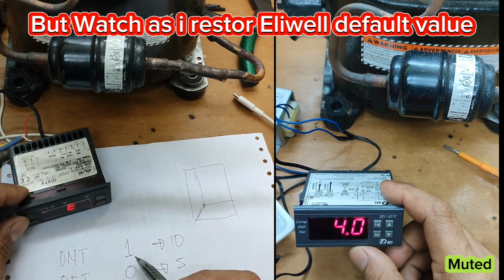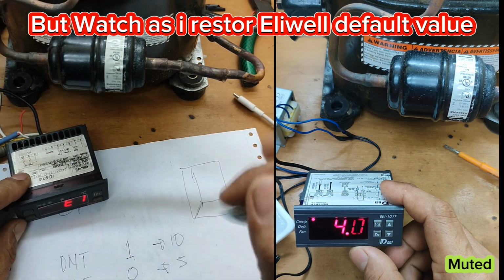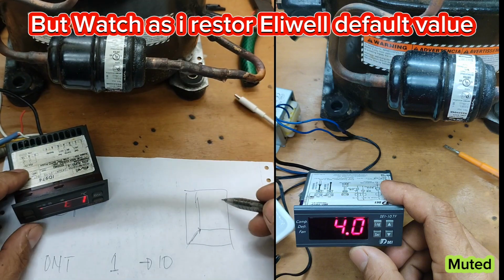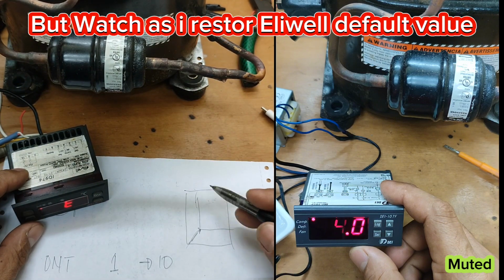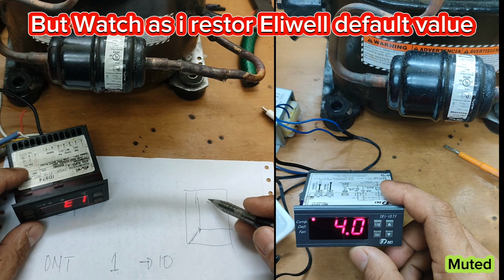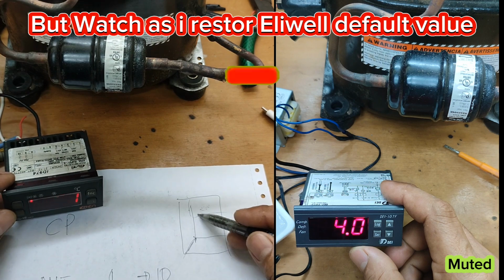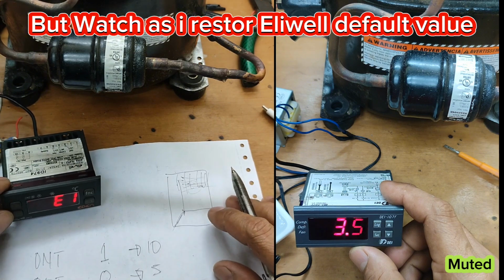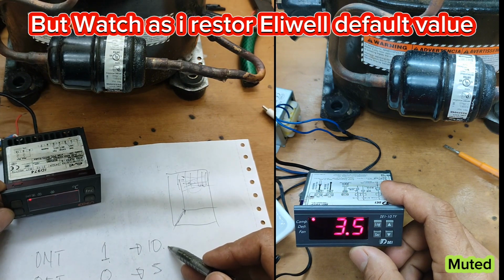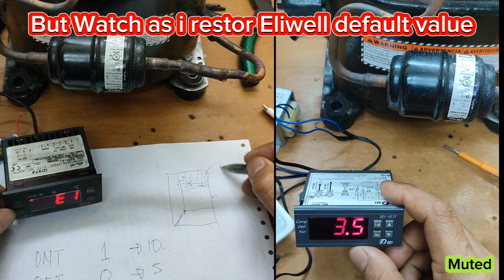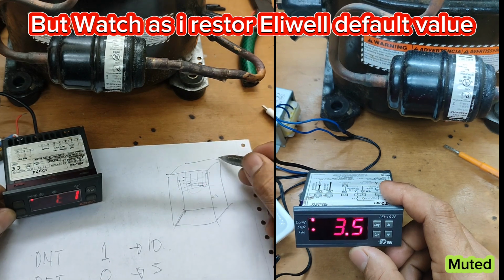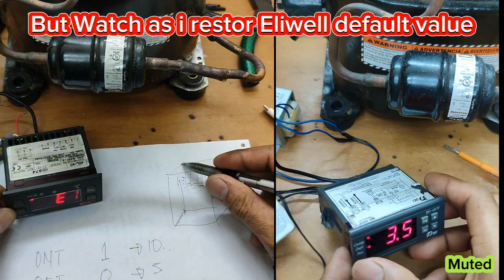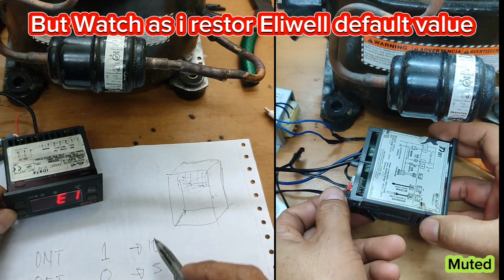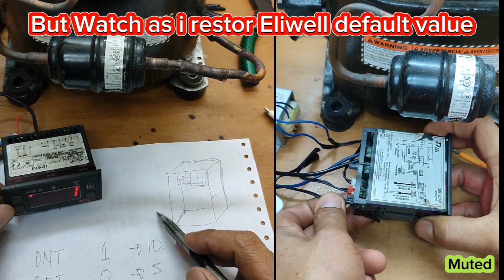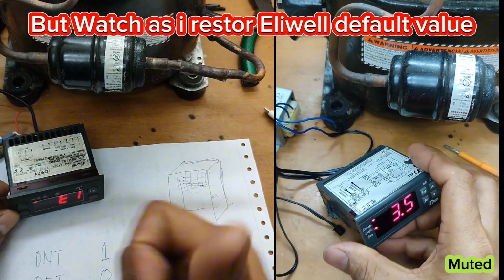The consequence of the compressor always being on during a faulty probe is ice buildup. You will accumulate ice formation on the evaporator fins, causing high temperature also. So I wanted to implement this in my unit, but the problem is it's not applicable for the Eliwell ID974, but it is for the Dixell.